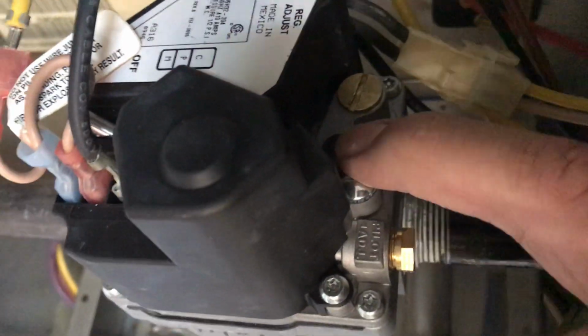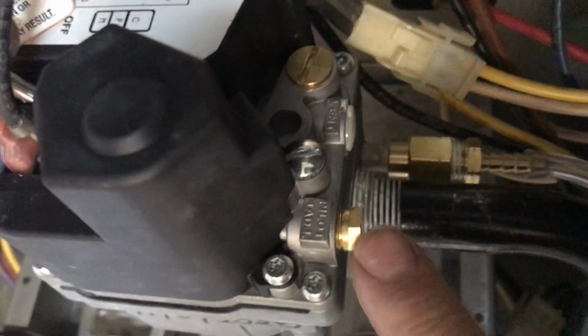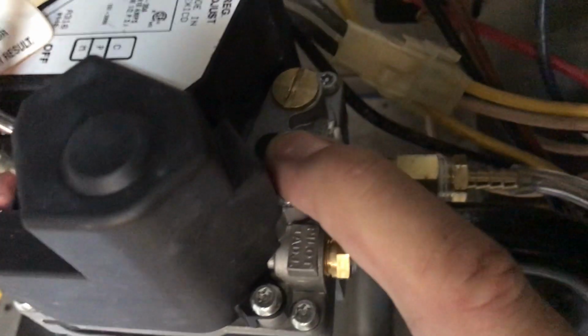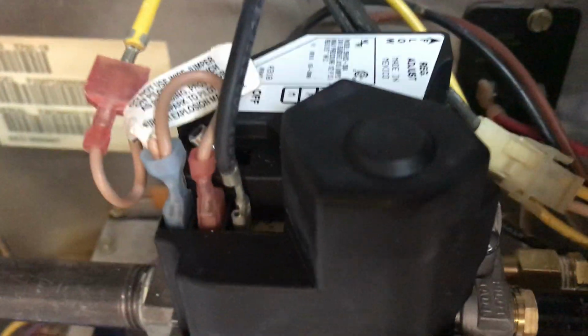The book does not call it a 2-stage. The part number doesn't. Say if it were a 2-stage, you would have another adjustment over here. So this is not molded through or not used, no cap. So this is for a pilot. If you had a pilot, this should have been a low side for 2-stage and a high side, but it's clearly acting like a 2-stage valve.